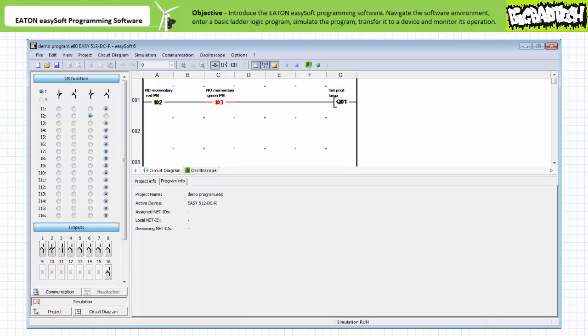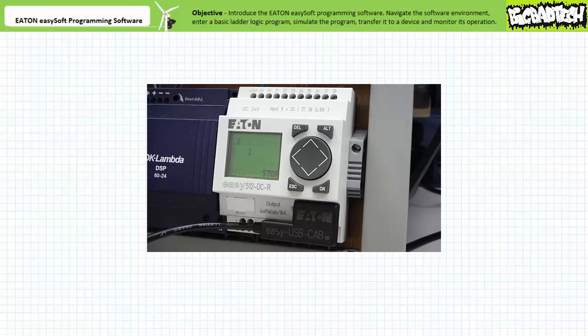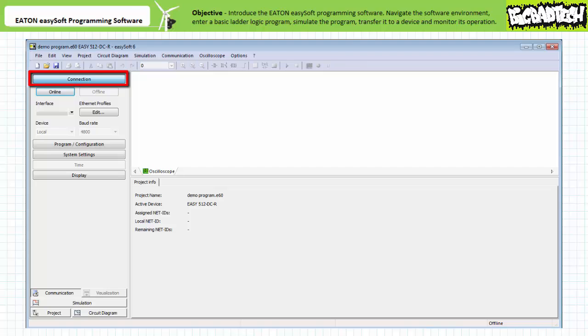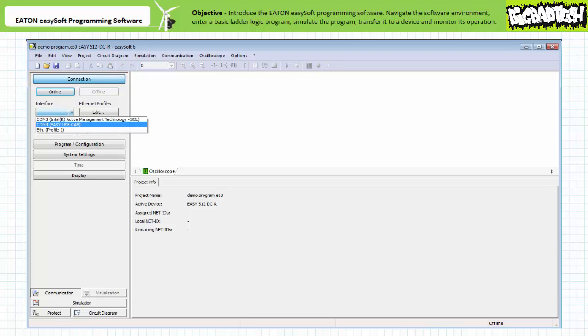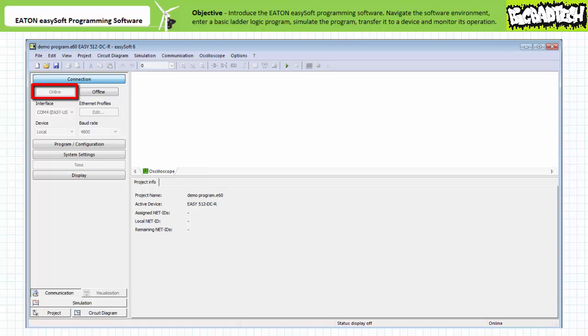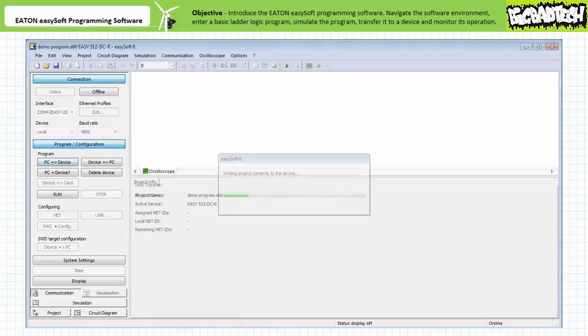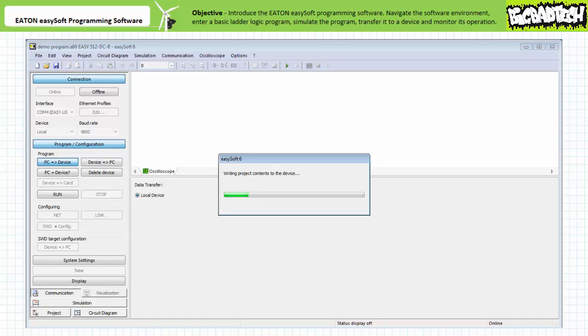The simulation utility has thus verified the functionality of our program in response to our intended field input devices. We can now save the program if we haven't done so already and transfer it to a device. To transfer the program to a device, power up the EASY512 Intelligent Relay, place it in stop mode and return to the status window. Open the port on the front of the device and install the communications cable and plug the other end into your computer's USB port. Open the communications window, expand the connection menu, and choose the COM port used by the EASY512 Intelligent Relay using the drop-down interface menu. Press the online function to connect the device to the PC. Once connection is established, expand program/configuration and press PC to device to transfer the program from the PC to the PLC. The EZSoft programming software now writes the contents of the active program onto the device.